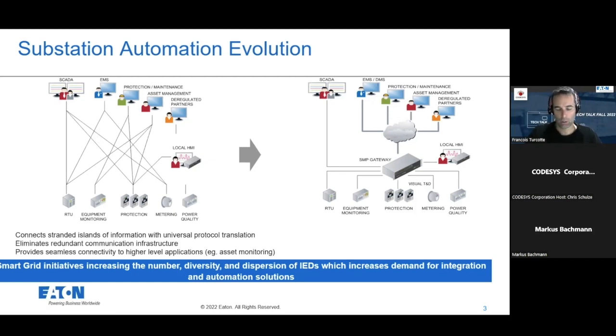So that's really the goal, to separate and secure this part of what they call a critical asset in their substation. And that's why most people use an RTU or that type of smart device to comply with what we call NERC CIP in North America, a standard made by the USA, but which, let's say, Canada and Mexico also have to comply with if they want to exchange electricity and connect to the grid.